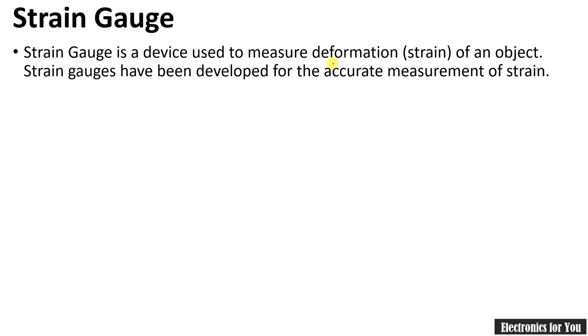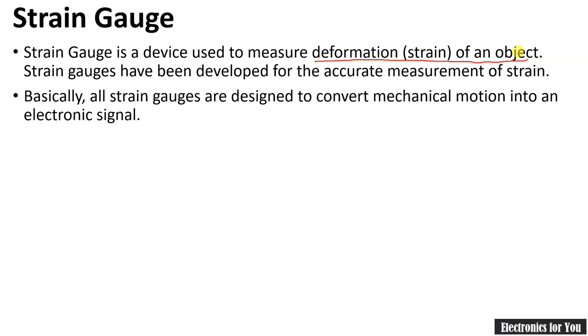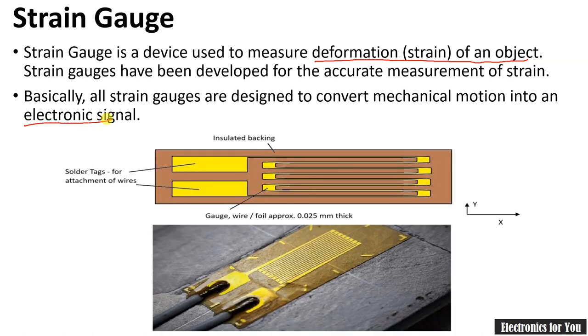Strain gauge is a device used to measure deformation, that is strain, of an object. It is a device which converts the deformation into an electrical signal, because this deformation causes a change in resistance which can be used for conversion into an electronic signal. This is the diagram for the strain gauge. Here we can see a wire wound in a zigzag pattern such that its length is increased. This is the gauge wire, which is approximately 0.025 mm thick, and these wires have two terminals which are soldered — solder tags for the attachment of wires.